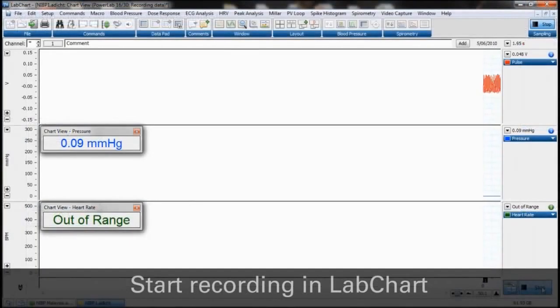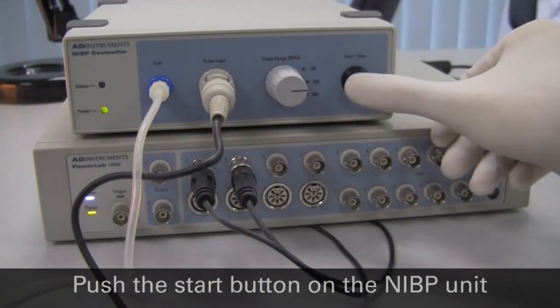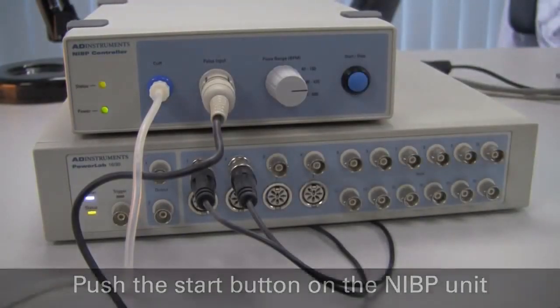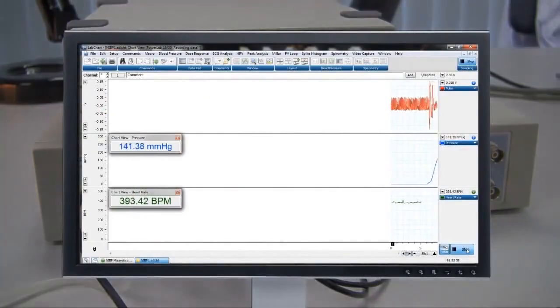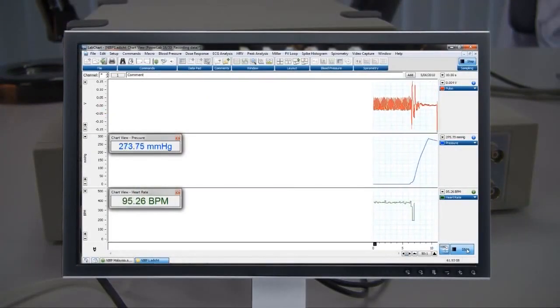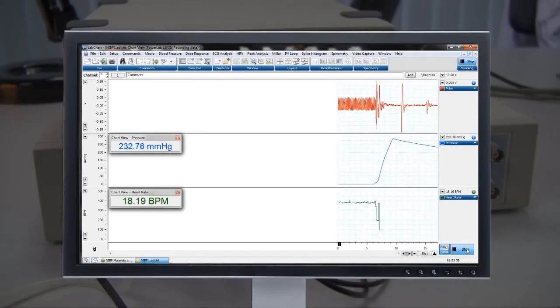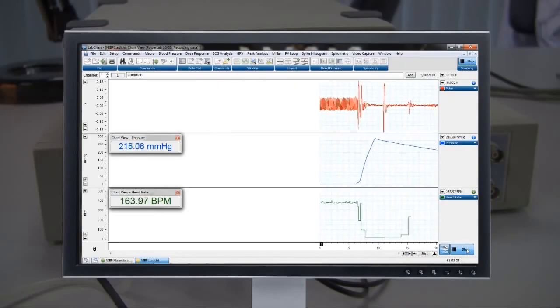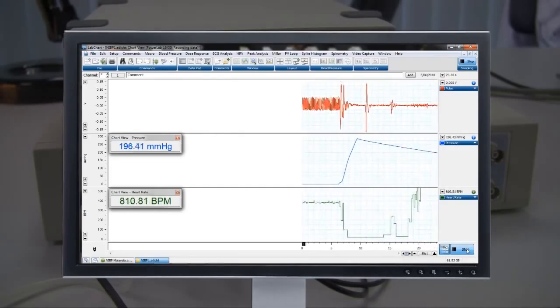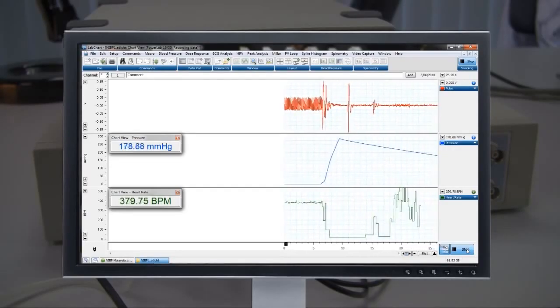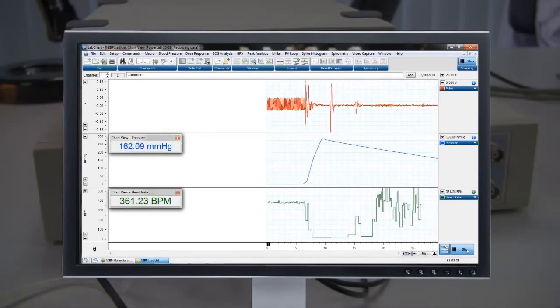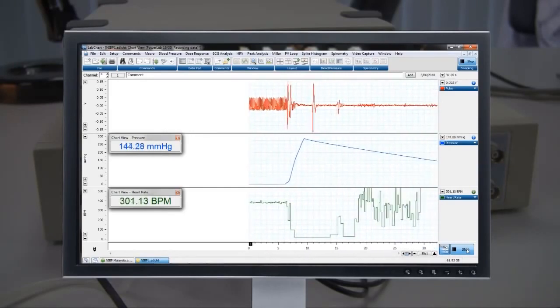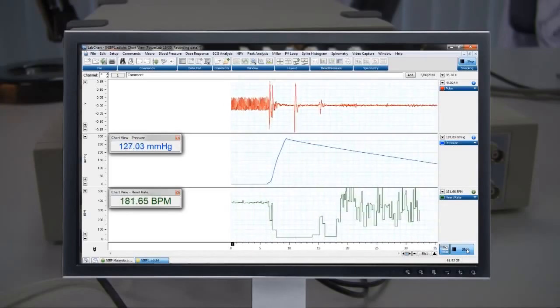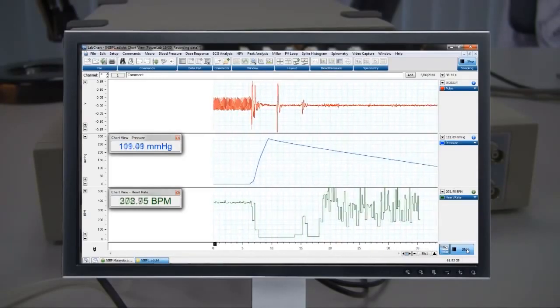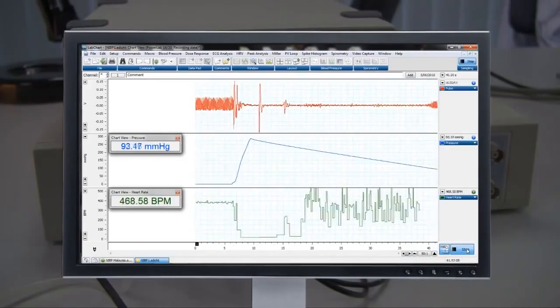Push the start-stop button on the front of the NIBP controller to begin a measurement cycle. The pump should start and the tail cuff should inflate. Observe that the pressure waveform climbs up to the preset maximum cuff pressure. The pulse signal should start to decrease as the cuff starts to occlude the blood flow. When the maximum cuff pressure is reached, the pump will stop and the pressure will begin to drop slowly. As the pressure drops, the pulse signal will start to increase again.